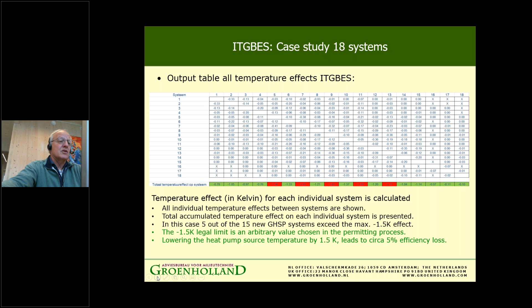Yeah, so the total effect on system number 1, I think, is 0.7. On system number 5, for instance, you can see that there is a larger effect on the system, and that is greater than the 1.5, let's say, degrees Kelvin effect that we allow in the Netherlands. And this 1.5 is an arbitrary value, but it was selected because a 1.5 K loss on your source temperature on your evaporator is about a 5% efficiency loss on the efficiency of your heat pump when it's generating heating.